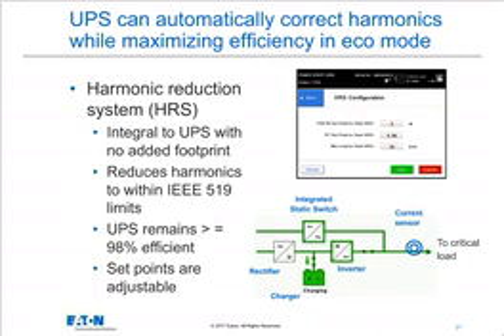But the result is we can use the suspended or the unneeded power conversion stages in the UPS while we're in eco mode to correct harmonics, so that you can take advantage of the high efficiency and not have to worry about problems interfacing with your generator, etc. Okay, moving to the next slide.